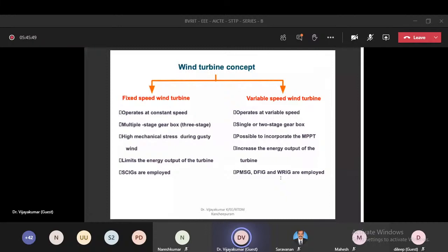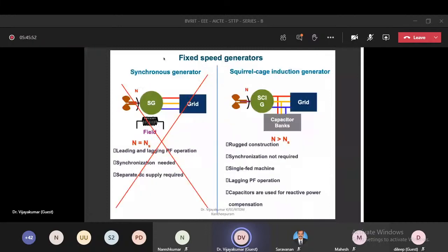When we come to fixed speed generators, normally in the wind turbine we won't use a synchronous generator. The reason is, if you want to generate power from a synchronous generator, you have to operate at a constant speed. If it's a 4-pole machine on a 50 hertz supply system, then you always have to rotate at 1500 RPM, right? You have to operate at constant speed. But in wind, that's not possible, right? At least you will get a 100 RPM difference. That's why you cannot use this machine as a generator.